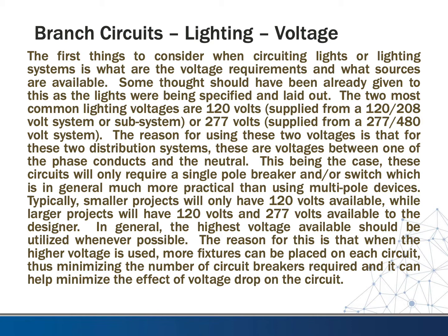Smaller projects will typically only have 120 volts available, while larger projects will have both 120 volts and 277 volts available to the designer. In general, the highest voltage available should be utilized whenever possible. When the higher voltage is used, more fixtures can be placed on each circuit, minimizing the number of circuit breakers required and helping minimize the effects of voltage drop on the circuit.